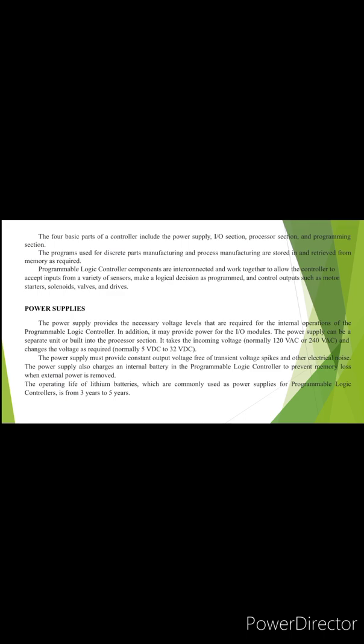Power supplies. The power supply provides the necessary voltage levels that are required for the internal operation of the programmable logic controller. In addition, it may provide power for the input and output modules. The power supply can be a separate unit or built into the processor section. It takes the incoming voltage, normally 120 volts AC or 240 volts AC, and changes the voltage as required, normally 5 volts direct current to 32 volts direct current. The power supply must provide constant output voltage free of transient voltage spikes and other electrical noise.